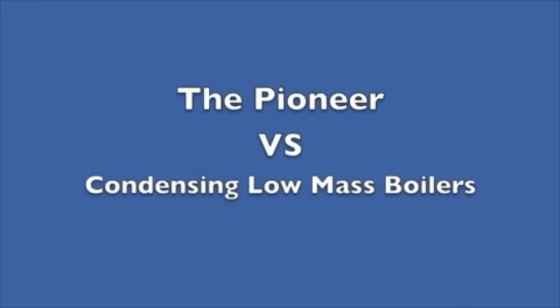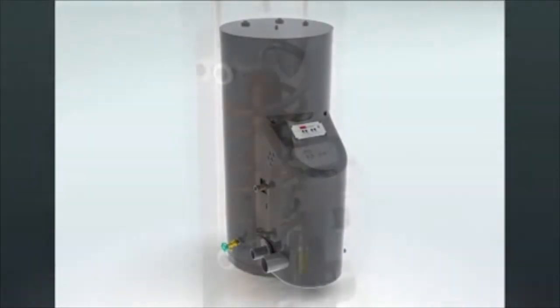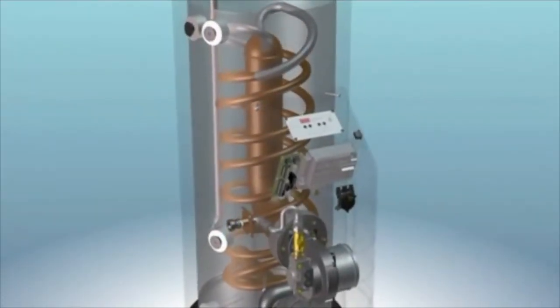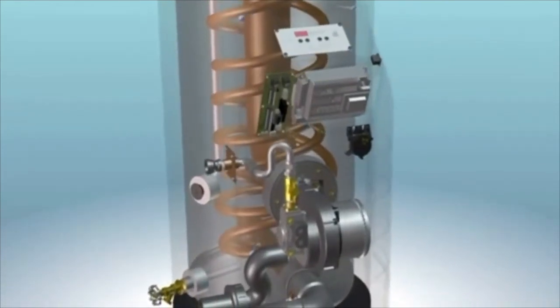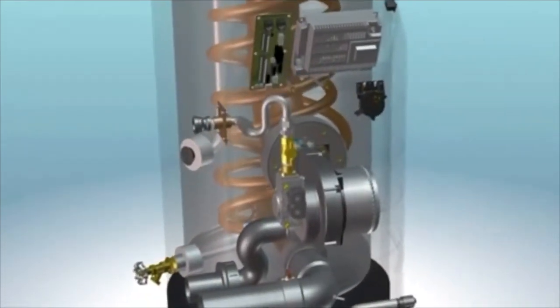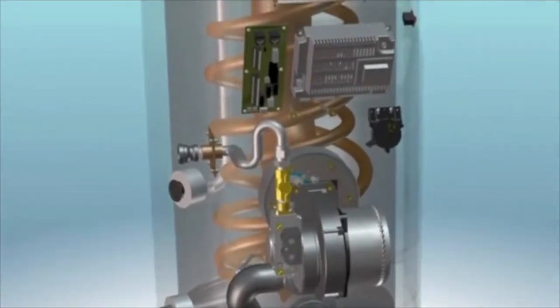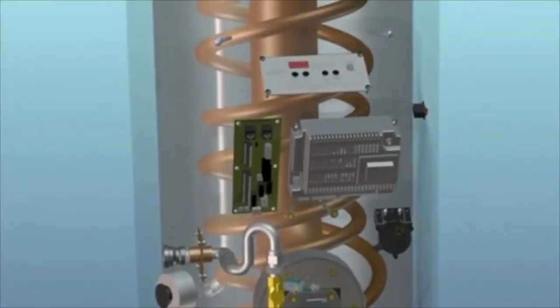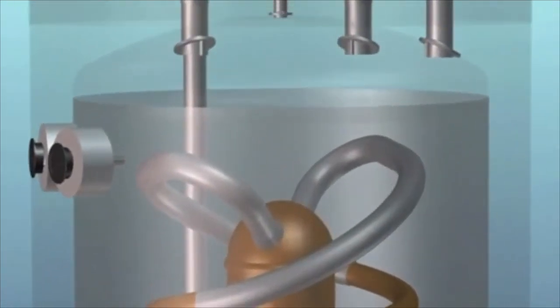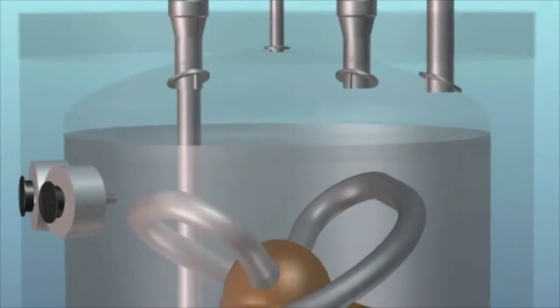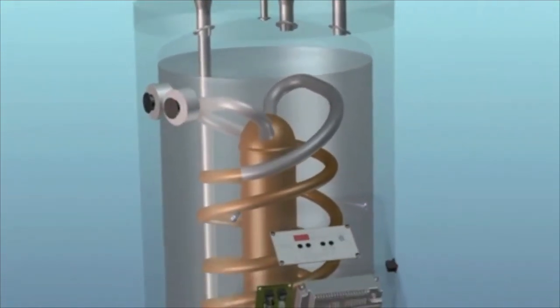The Pioneer versus condensing low mass boilers: to put it simply, the Pioneer has all the major features, including the same highly efficient combustion and controls technology of the leading low mass condensing boilers. Having ample thermal mass to compensate, the Pioneer does not ever require primary secondary piping setup. The Pioneer is piped like a tank type water heater or a mid-efficiency cast iron boiler. Many of the components such as the boiler pump, as well as the boiler loop piping and labor required on condensing low mass boilers, are eliminated.